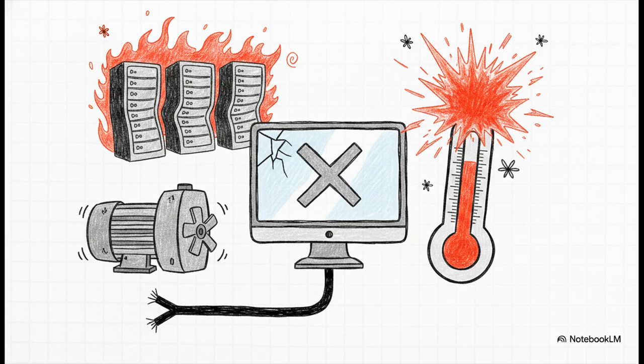The exact second the computer crashes and the voltage drops to zero, the pump's contactor instantly opens. Those massive industrial water pumps just grind to a halt. Thousands of gallons of chilled water stop flowing. Without that cooling, the ambient temperature in the data hall spikes immediately. Within a matter of minutes, millions of dollars of server hardware would literally start melting down. Data's lost, websites go totally dark, financial networks crash. And all of that just because a computer froze.